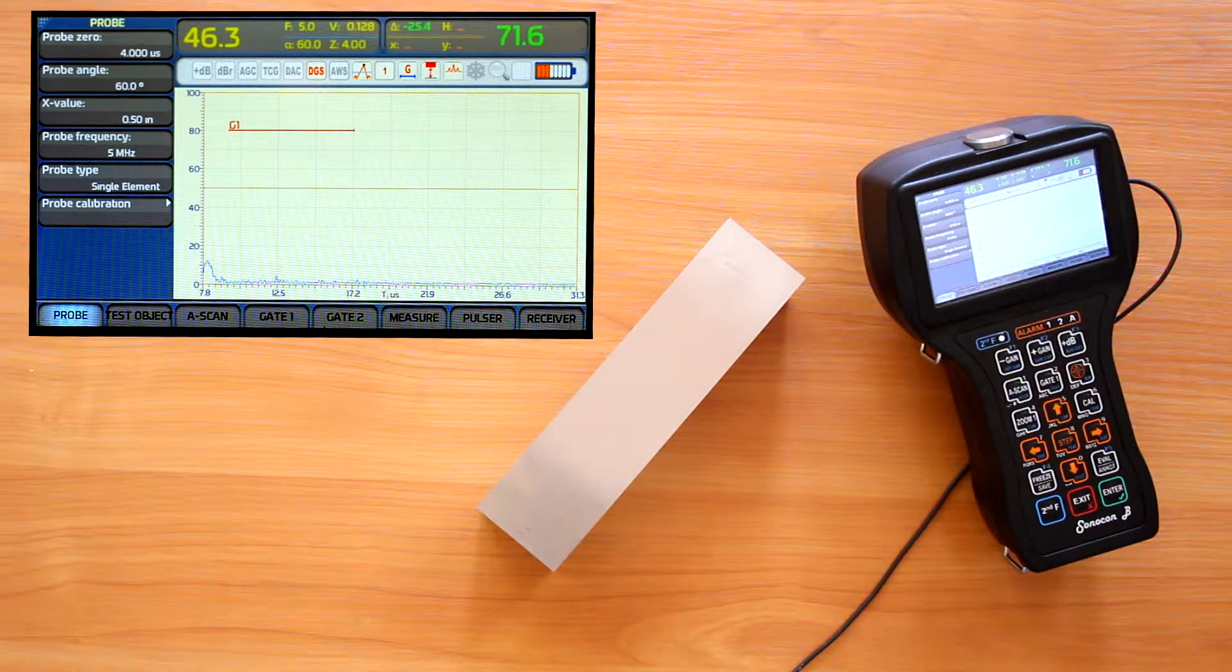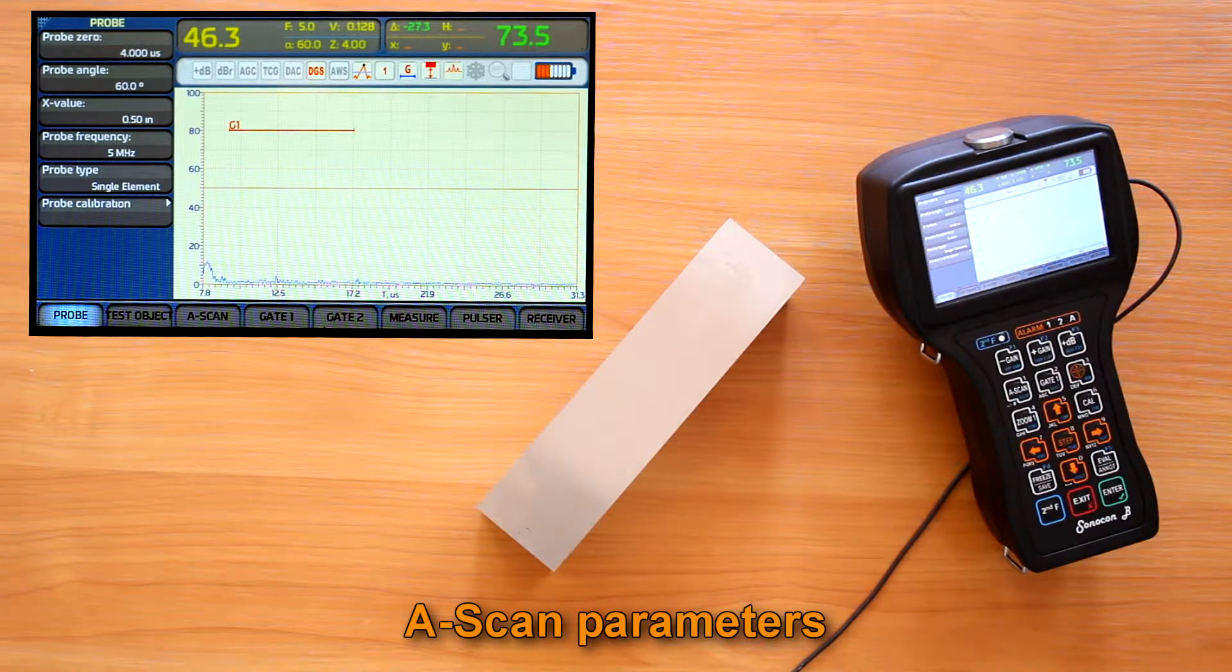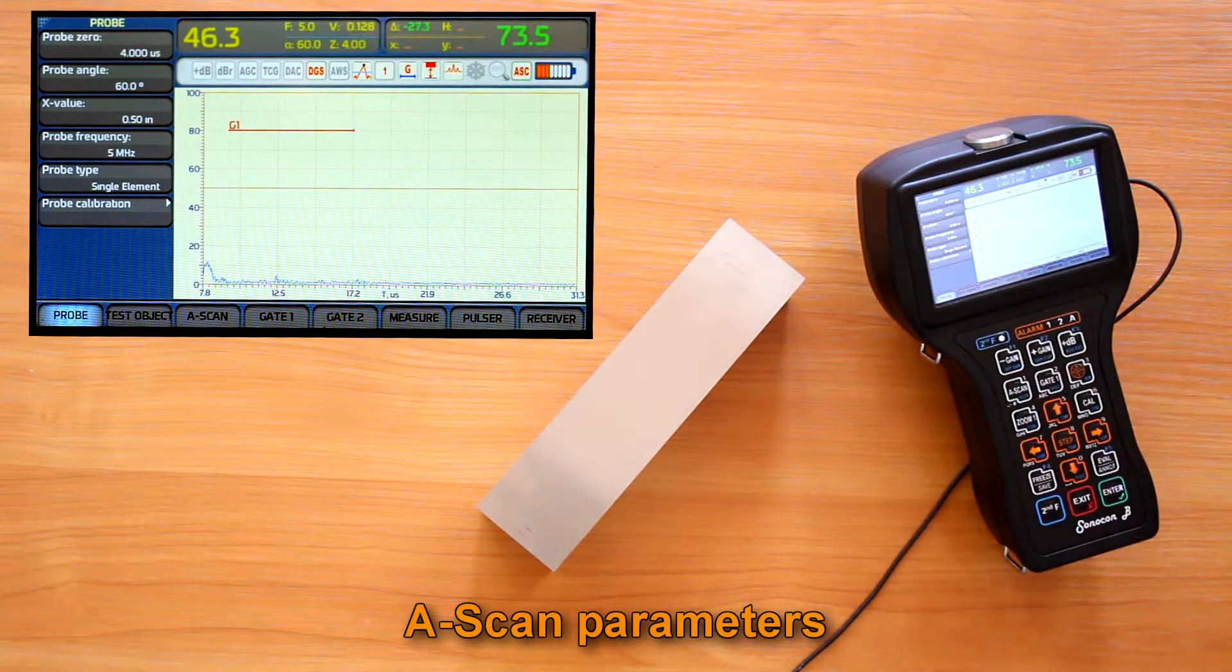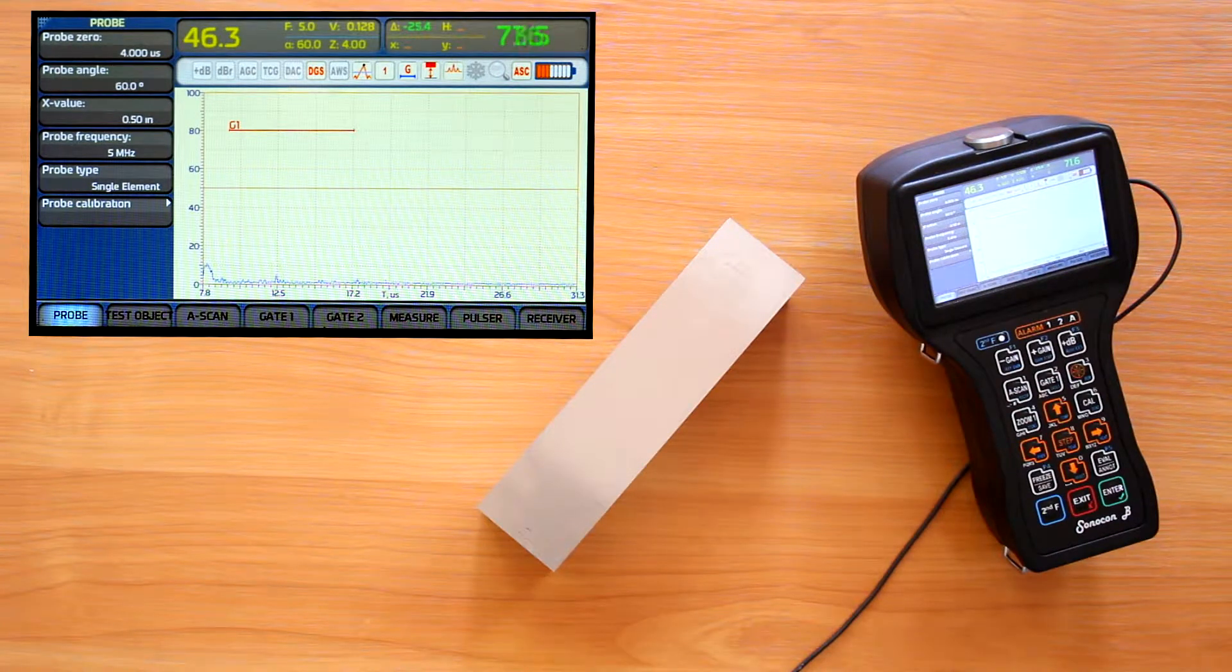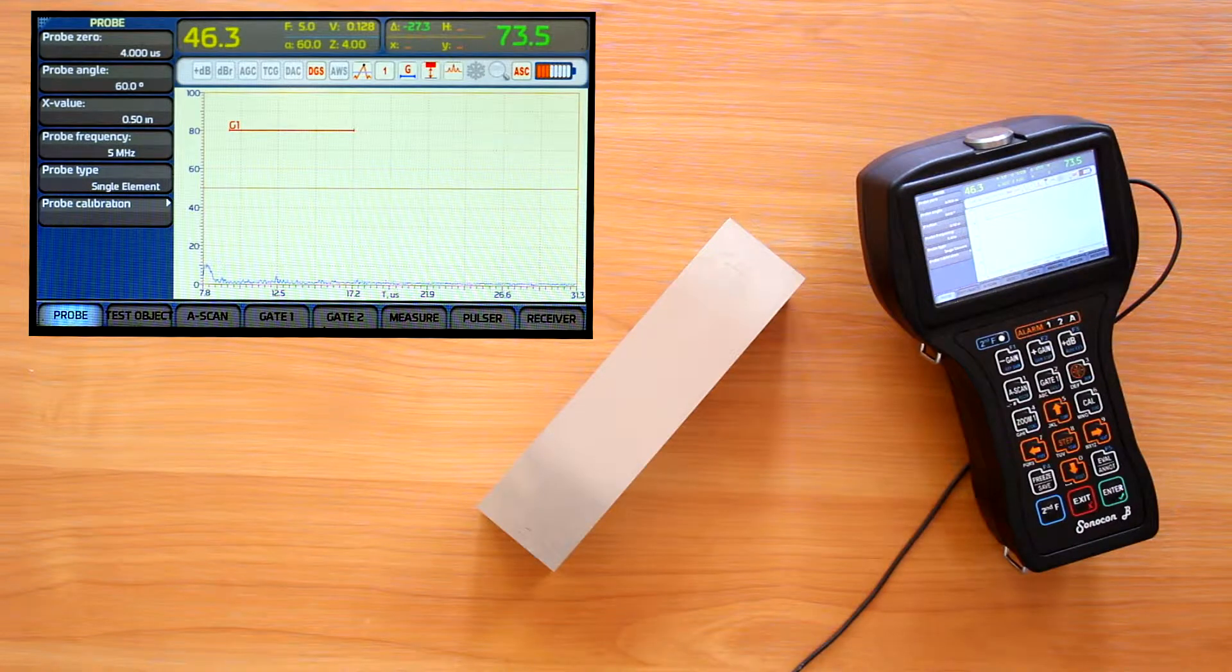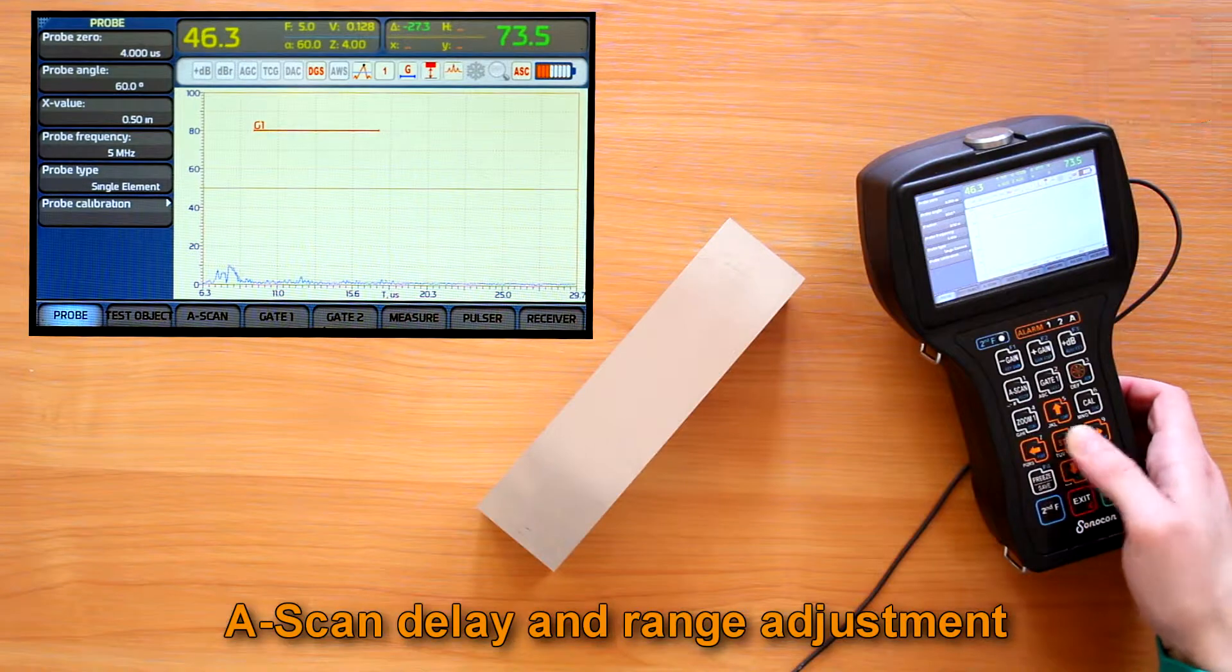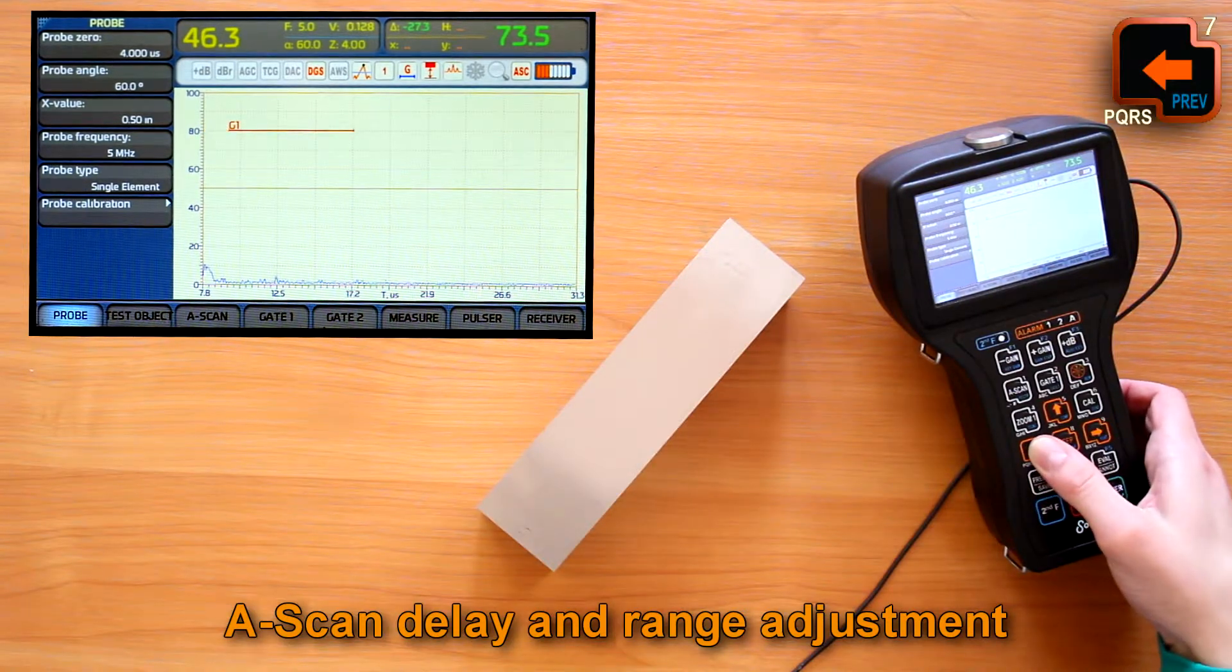Another important group of settings are A-scan parameters. To drive the A-scan I press the A-scan button. The A-scan indicator shows we are in the A-scan direct control mode. Now we can move the A-scan window right or left with right and left arrows, adjusting A-scan delay parameter.